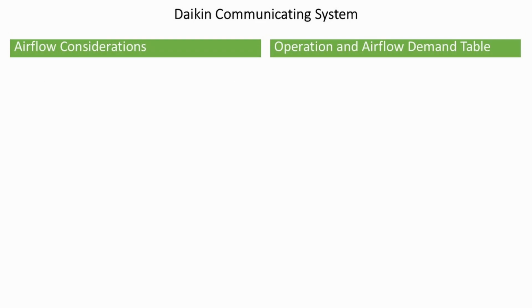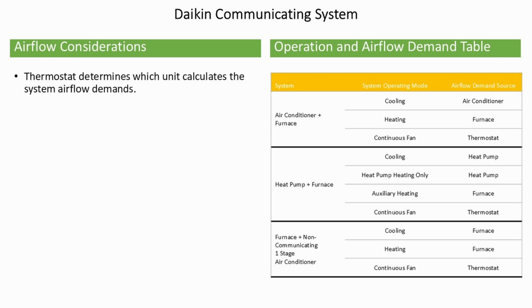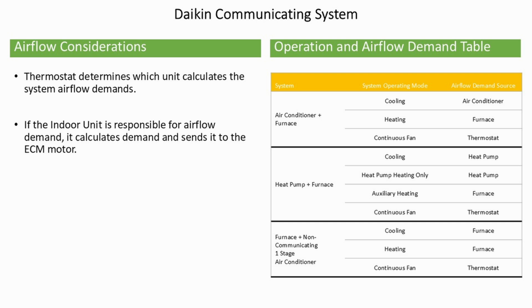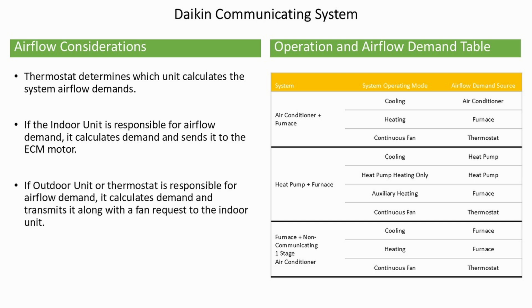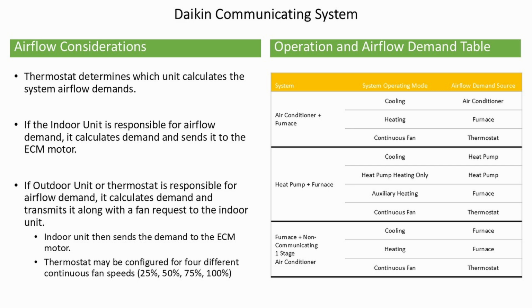Airflow considerations and operation and airflow demand table. The thermostat determines which unit calculates the system airflow demand. If the indoor unit is responsible for airflow demand, it calculates demand and sends it to the ECM motor. If the outdoor unit or thermostat are responsible for airflow demand, they calculate demand and transmit it along with a fan request to the indoor unit. Indoor unit then sends the demand to the ECM motor. The thermostat may be configured for 4 different continuous fan speeds: 25%, 50%, 75%, or 100%.